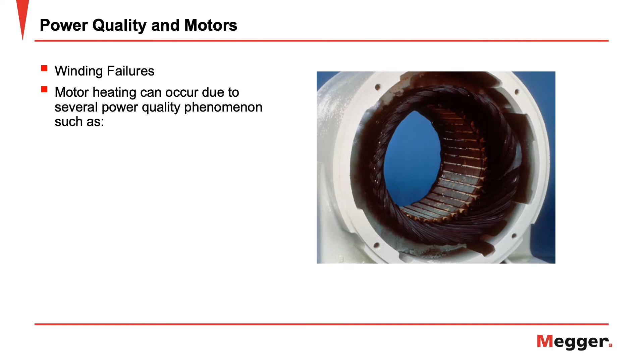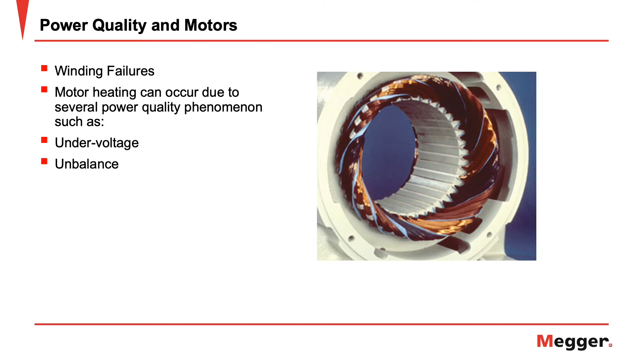Unbalance. Just a 1% unbalance in the phase voltage can lead to a 6 to 10% unbalance in phase current. This current unbalance will generate unbalanced heating effects in the coils. This leads to uneven phase heating. Depending on the winding configuration, Y or delta, a phase or two, respectively, will be heated more than the others. This can lead to failure of these coils.